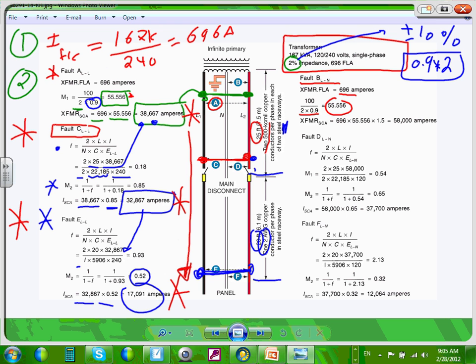Then you have to multiply by the formula. This is by this number. They want you to use this number, 1.5. I put a question mark on this. They want you to increase it 50%, because a ground fault could be under certain circumstances higher than a short circuit. Highly unlikely. So you end up with a 58.